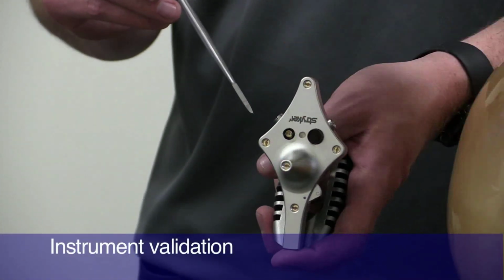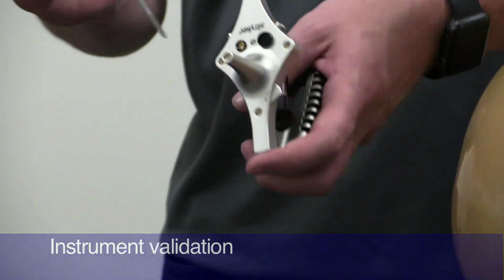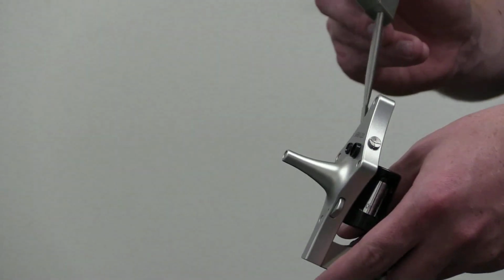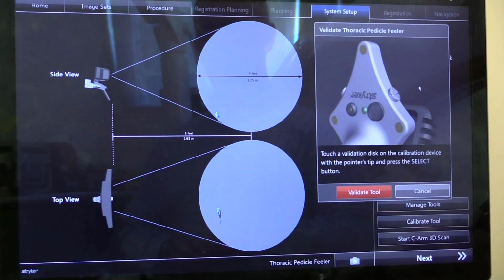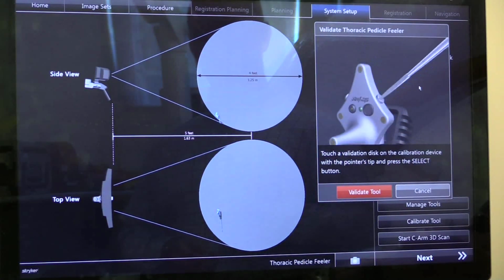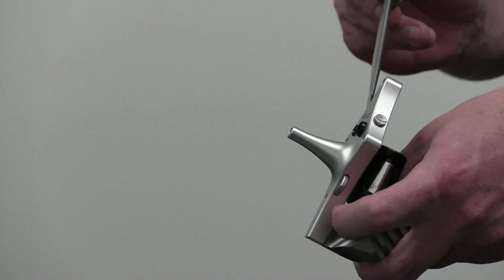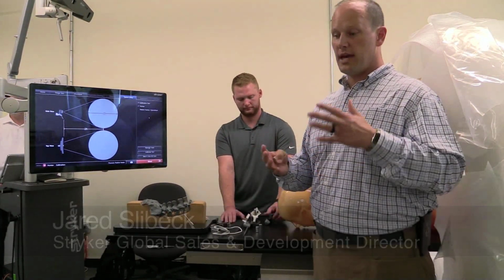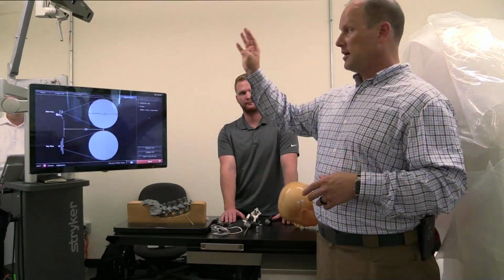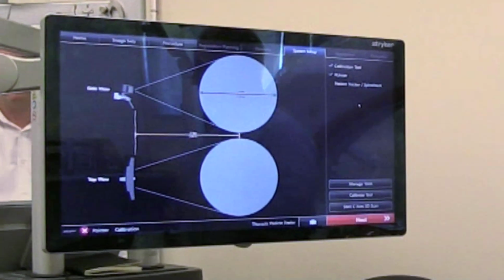So he'll point this device and this device towards the camera. He'll place it into the divot, and then he'll press the button one time either here or here, and it will validate. So no matter what we're attaching to, if it's rigid or non-rigid, if you can't repeat those 2 steps, it won't even let the instrument enter the field.